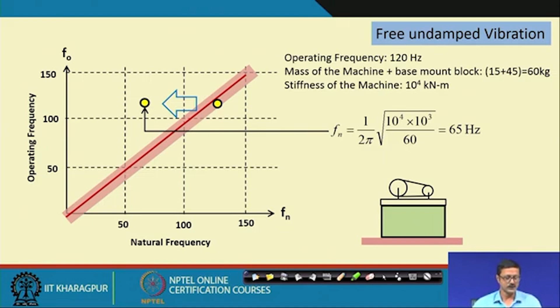So the point shifted over here. Why did this point shift? Because I attached an additional load of 45 kg to the machine by virtue of the mounting and inertia block, which will reduce the natural frequency, and now the natural frequency and operating frequency are not matching with each other.